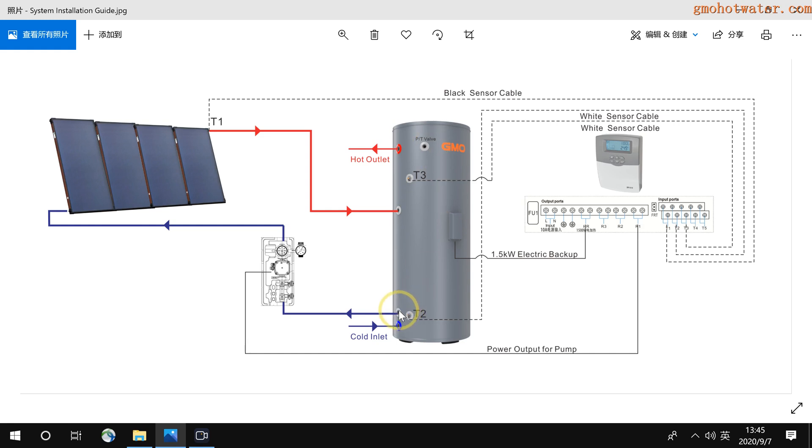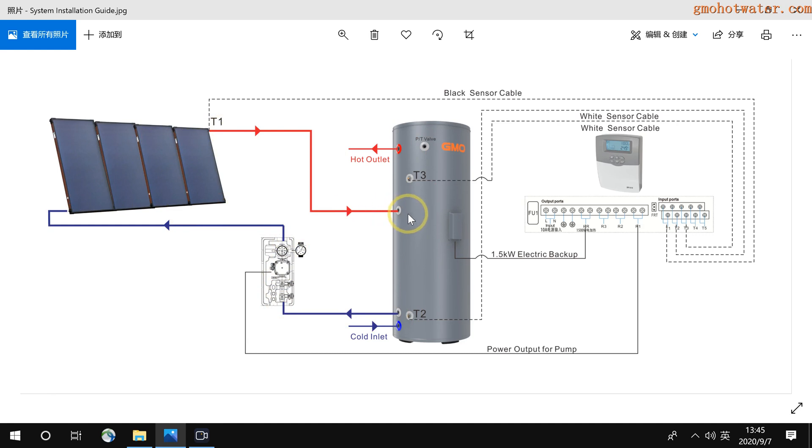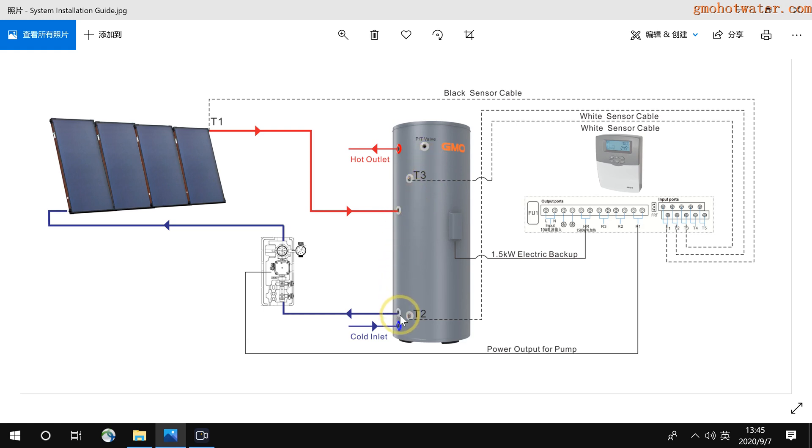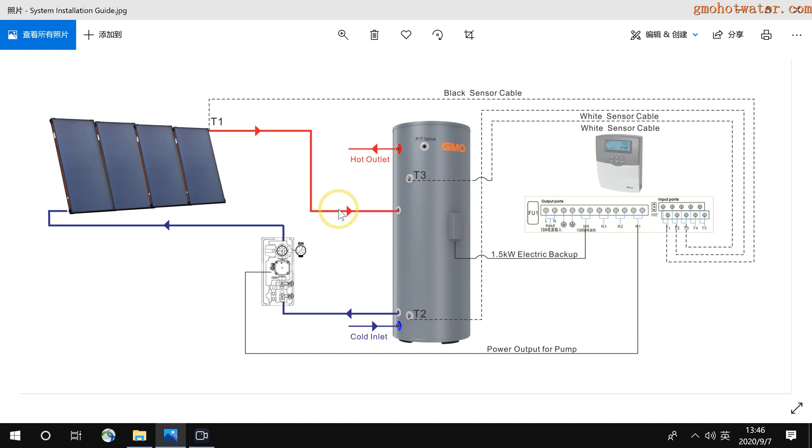And here is the cold water outlet to the pump, then return to the hot water to the tank. Because the hot water is always on the top of the tank, so when you install the system, you must guarantee the water to the collector is from the bottom connection here, and then return to the top connection here.